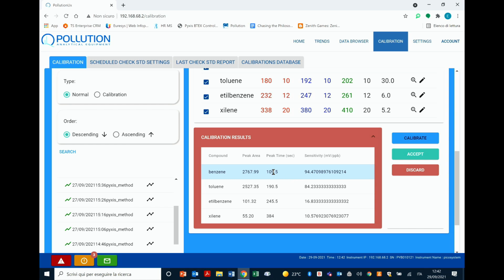Automatically, the instrument will give you the peak area, the retention time of the peak, and the sensitivity, which means basically the connection between the millivolts, so the signal of the PID, and the ppb, which is the concentration of the compounds. By then pressing accept, the new calibration will be accepted and the instrument will be updated.